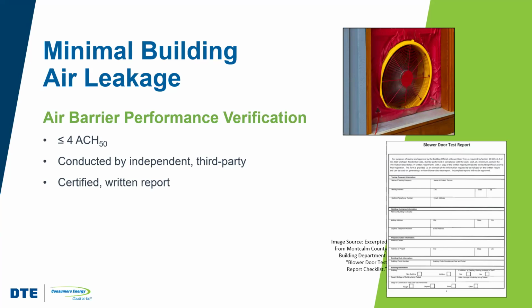We measure building air leakage with a blower door. Now, the blower door consists of a frame and a flexible panel that fit into the doorway, a variable speed fan to develop the differential pressure, a digital pressure gauge to measure the difference in pressure from the inside to the outside of the home, and a manometer to measure airflow. The test is conducted by an independent third party, and the maximum allowable leakage rate for minimum good design is 4 air changes per hour at a differential pressure of 50 pascals.